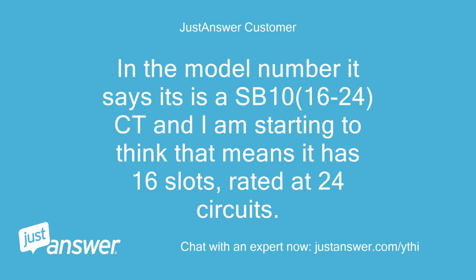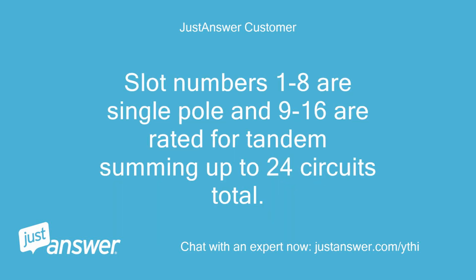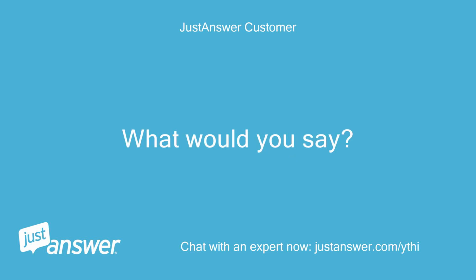In the model number it says it is a SB1016-24 CT, and I am starting to think that means it has 16 slots, rated at 24 circuits. Slot numbers 1 to 8 are single pole and 9 to 16 are rated for tandem, summing up to 24 circuits total. What would you say?